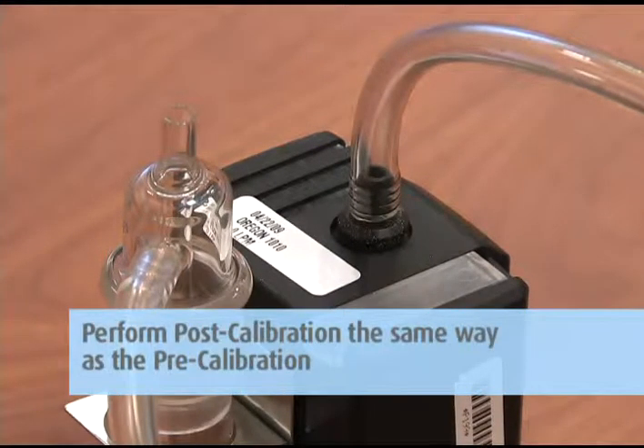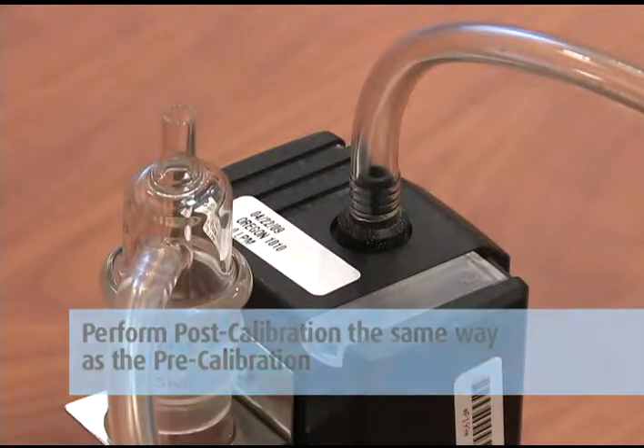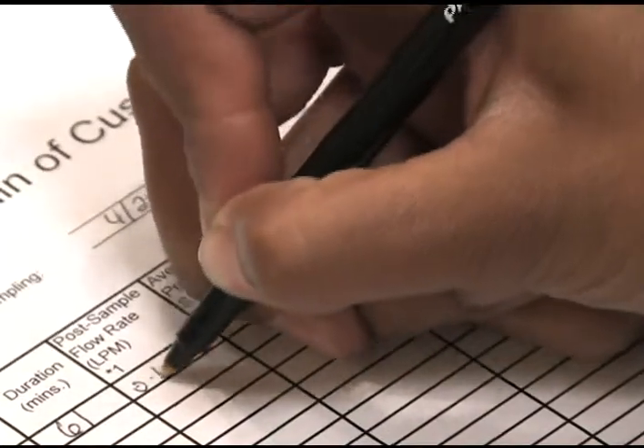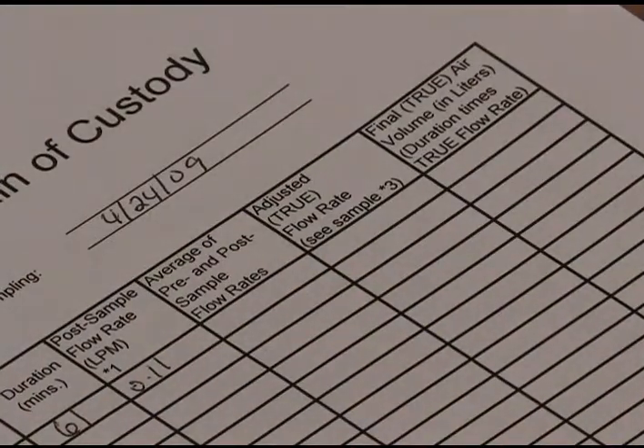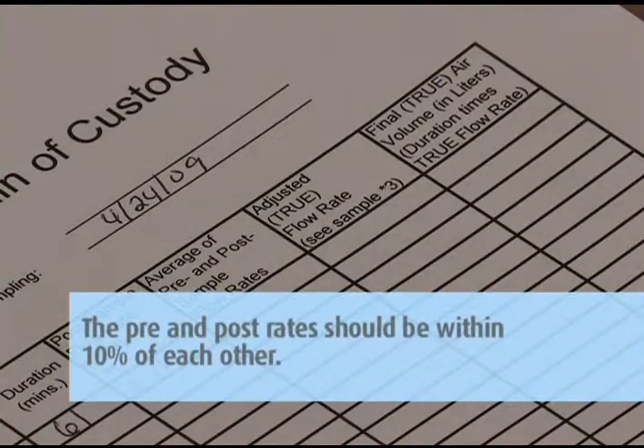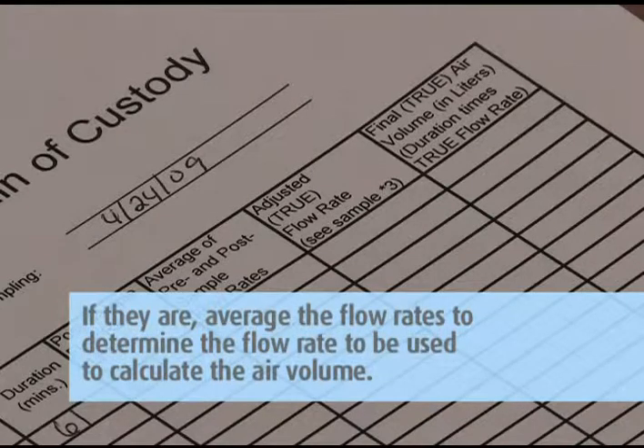You can now perform the post-calibration the same way you did the pre-calibration, using the marked impinger solution, but do not make any set screw adjustments. Just record the flow rate on the pump calibration sheet. The pre and post rates should be within 10% of each other. If they are, average the flow rates to determine the flow rate to be used to calculate the air volume.